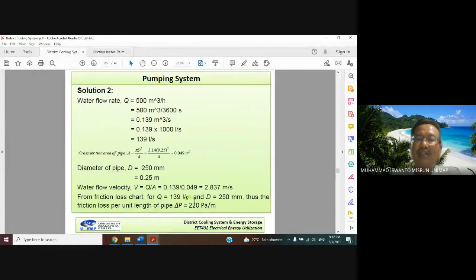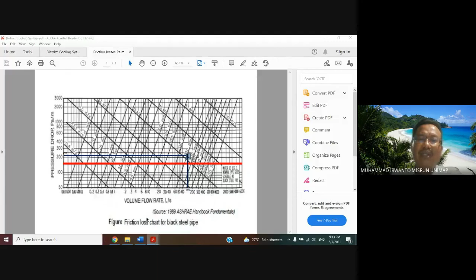Okay, and then the diameter of the pipe is 250 millimeter. The 200 millimeter is this one, the dashed line, and this dashed line is 250 millimeter. Okay, and then Nur Saibah, can you draw one line from the 139 until it arrives at this line for 250. This is the point. And then from here, draw one line to the vertical axis. So we obtain the value of pressure drop, which is 220 Pa per meter.